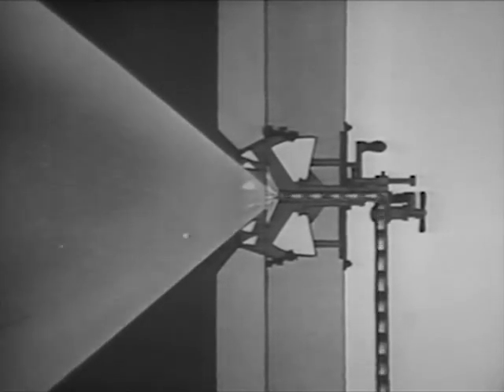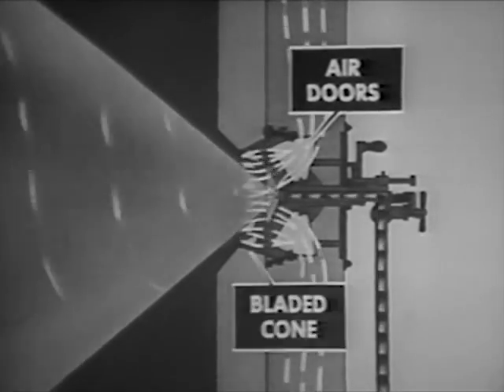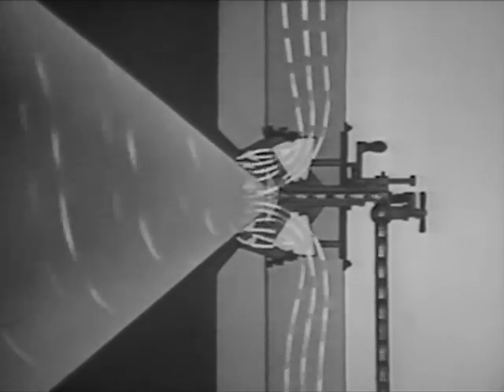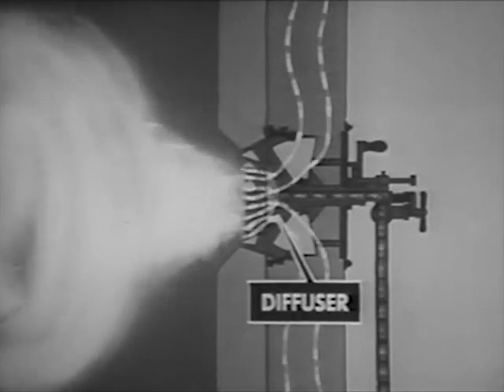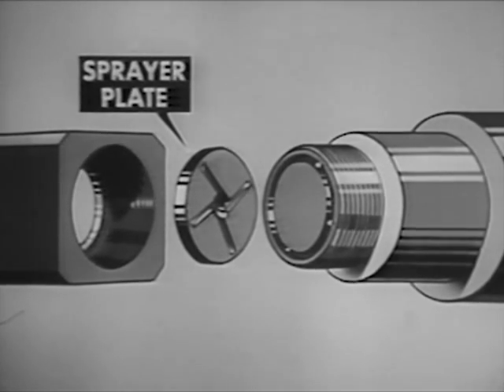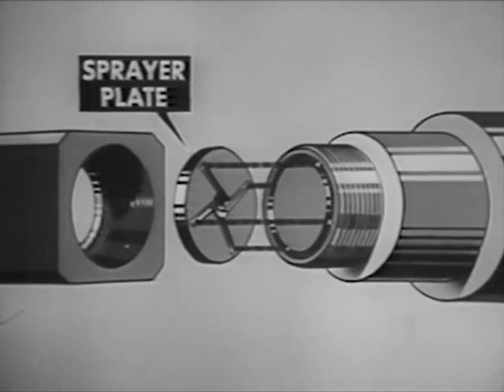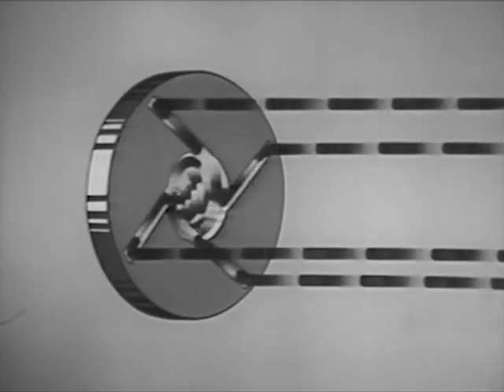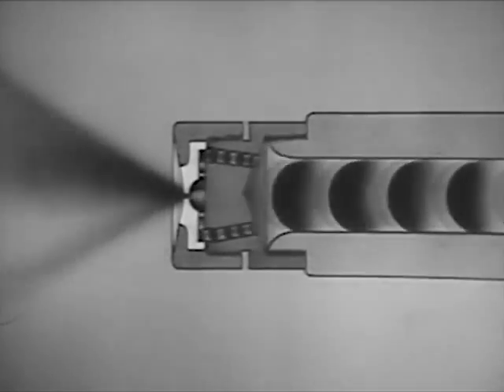Meantime, in the burner register, air provided by the force draft blower is given a rapid rotating motion by the air doors and bladed cone and mixed with the oil spray. The mixture of oil and air enters the furnace where combustion takes place. The diffuser prevents the air blast from blowing the flame from the atomizer tip. Now let's see the action of the sprayer plate in more detail in an exploded view. You can see how the oil passages in the atomizer nozzle guide the oil into the slots of the sprayer plate, how the slots give the oil a very rapid whirling motion in the whirling chamber, and how the whirling oil emerges from the sprayer plate orifice, or opening, as a hollow cone of mist-like oil particles.